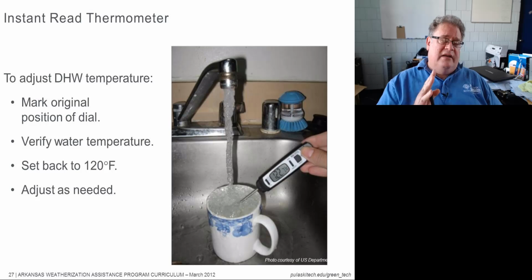The reason we're concerned about this is scald injury. It takes minutes at 120 degrees to cause an injury to the skin. However, temperatures above that, you start getting down to the seconds and even milliseconds at 180 degrees. You have a burn, possible third-degree burn, before your brain even registers that you've touched hot water. So by the time you go, ouch, that's hot, you're already burned. And this is especially true for children under 12 and for seniors that are approximately 60 years old and older. Some seniors get into this issue a little bit beforehand.